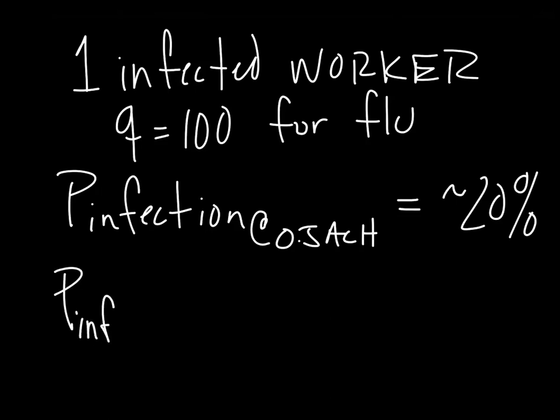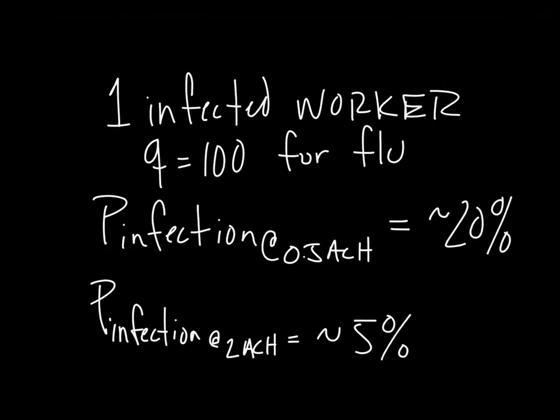If we increase the air change rate to 2 air changes, or 4,248 CFM, the number of potential infected co-workers decreases to roughly 5 percent, or 3 co-workers.